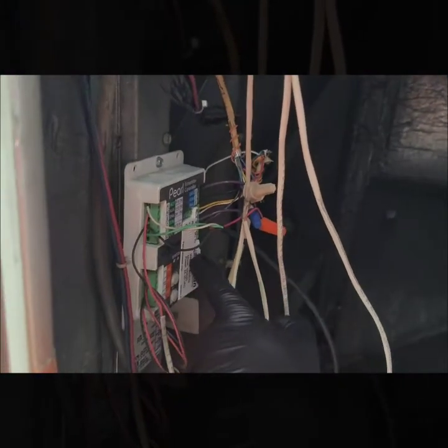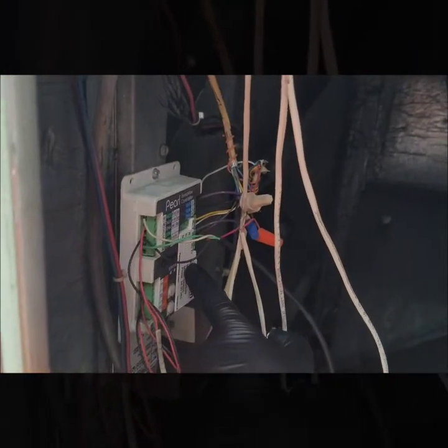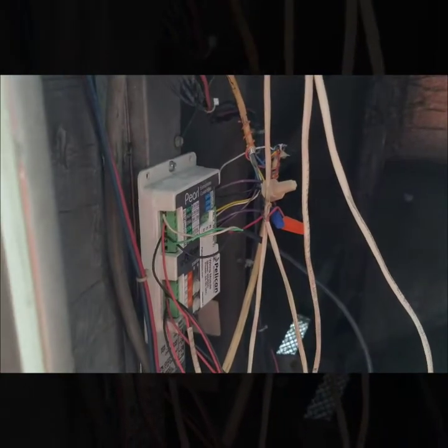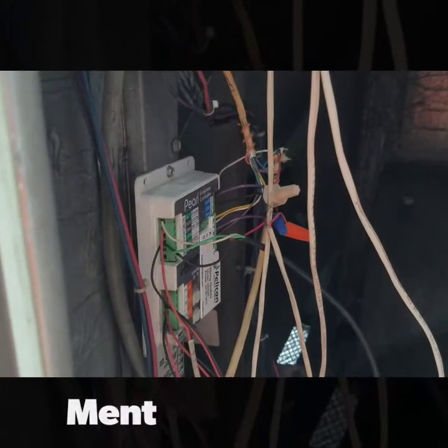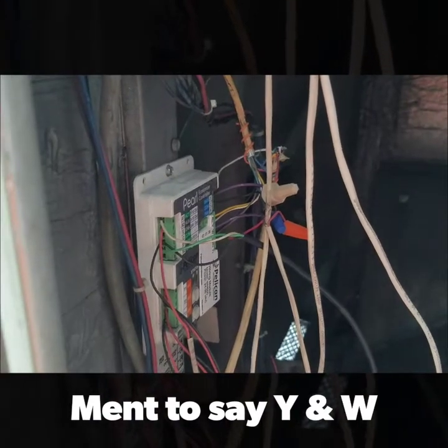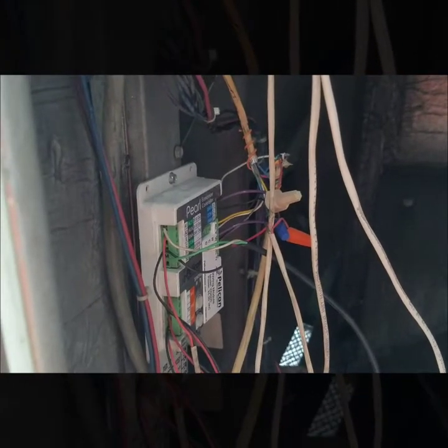The one issue we've been running into with them is these little relay packs - the little contacts inside are welding closed. When that happens, say you have two that are welding closed like a Y and a W, so your heat and your cool setting, it just locks everything out.